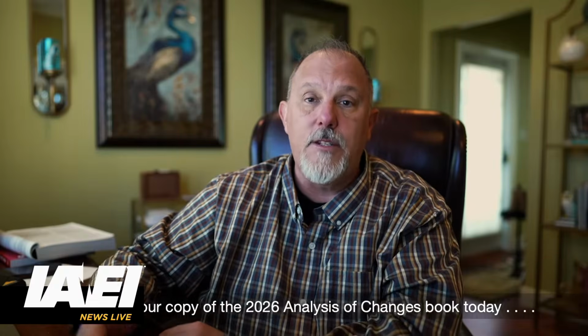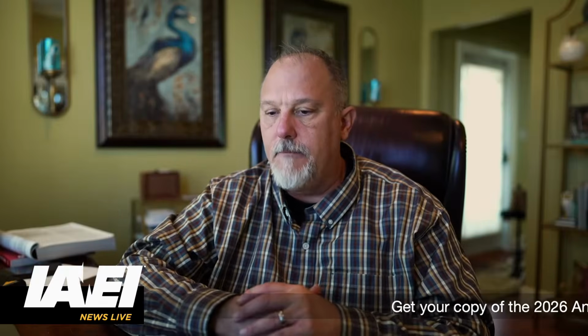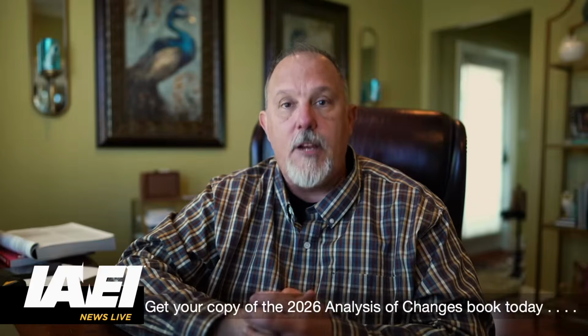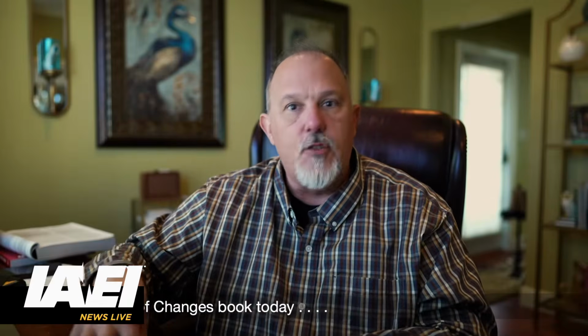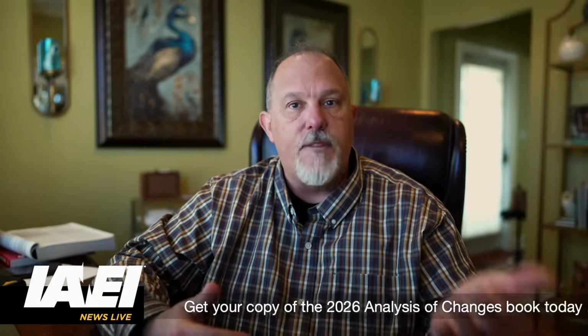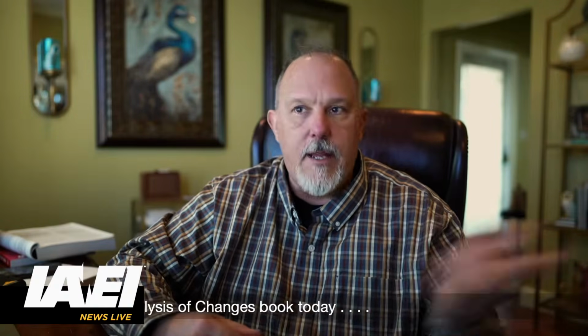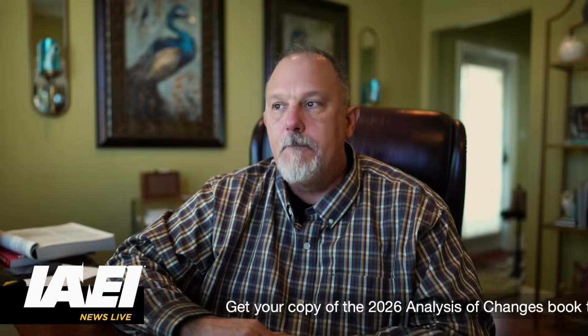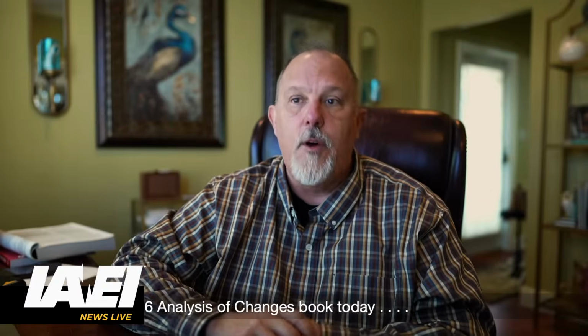But what they'll typically require is that you go pull the studies before you do the work. So it's a much more controlled environment than, say, as David Williams pointed out, commercial facilities. Say you go to a school. You may not have that same level of individual working on that power system, nor the resources at that school to have all of that study information and police it, right? But if I'm at a DuPont or an Olin Chemical or a PPG or a Ford plant, those larger industrial installations, especially if they're very in tune with 70E, will have a lot of procedures and policies in place to address that. Not all of them will.